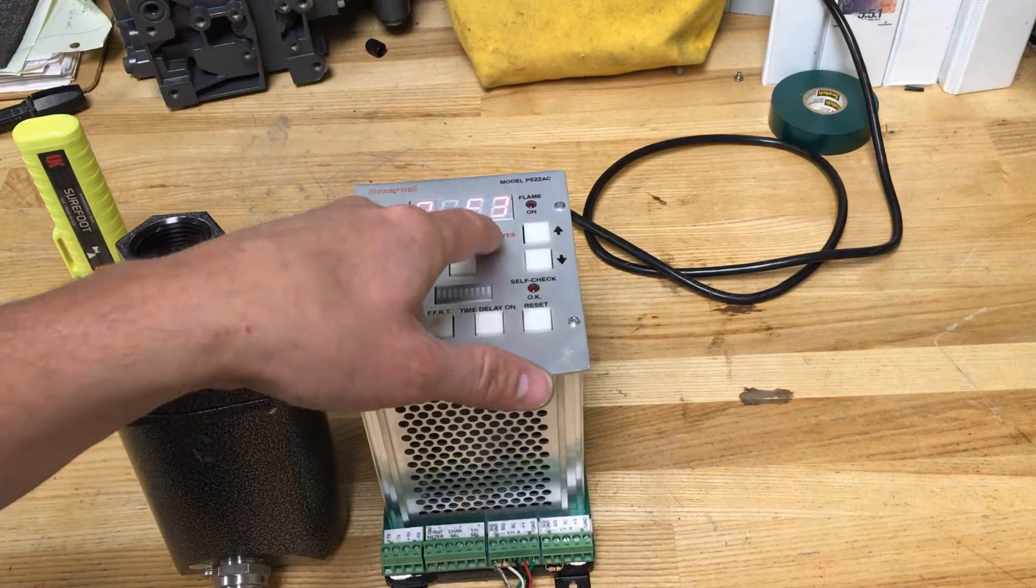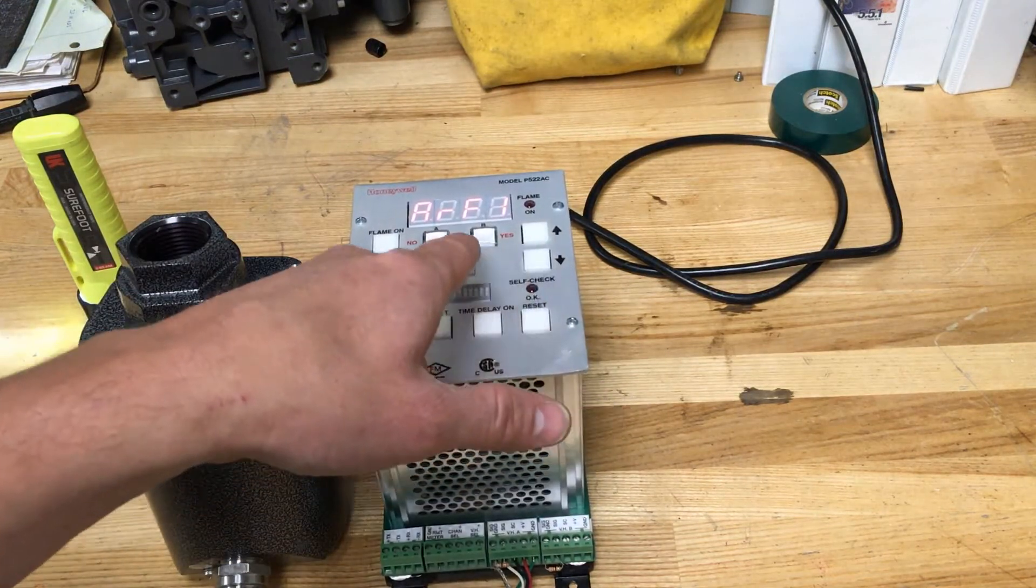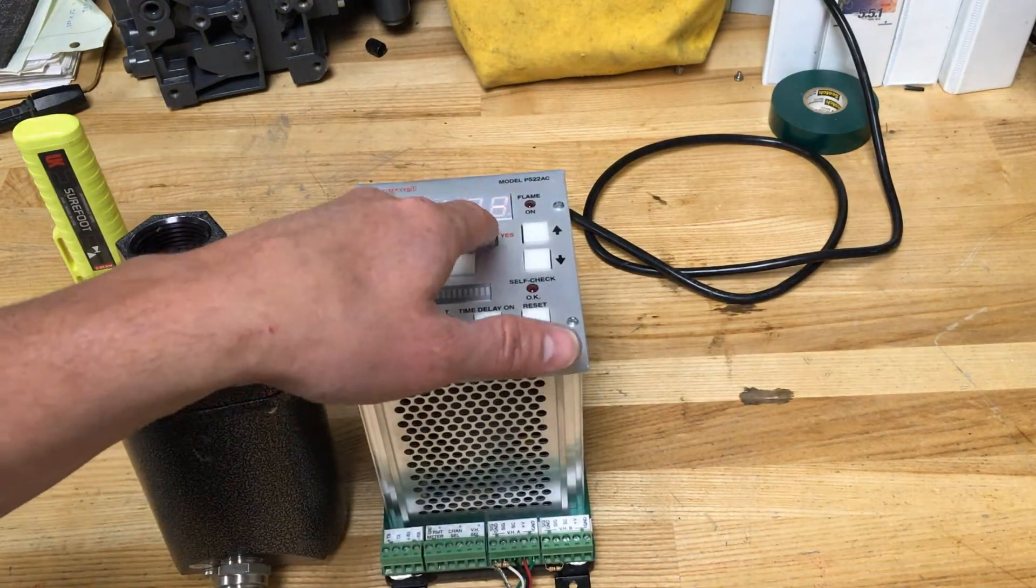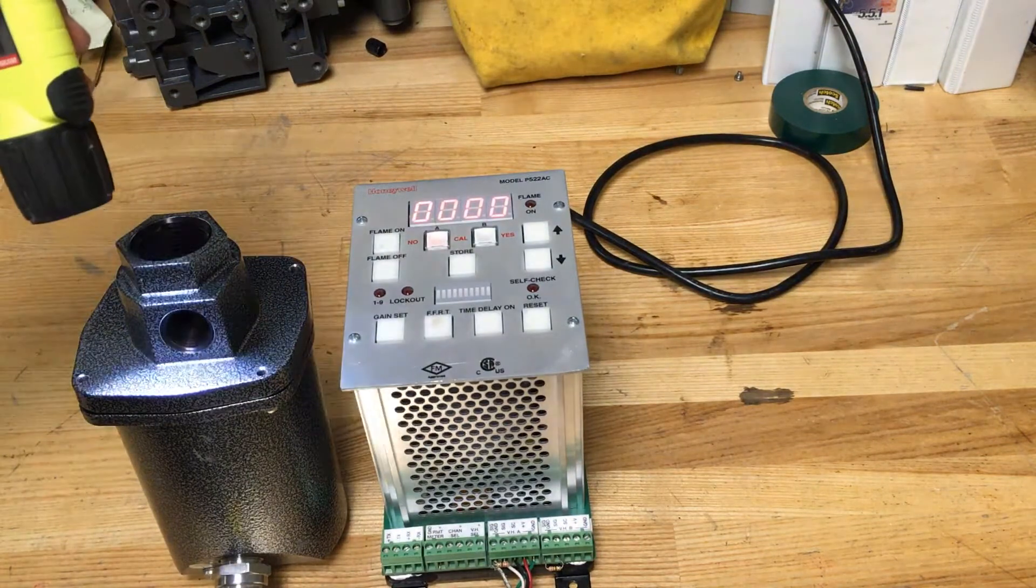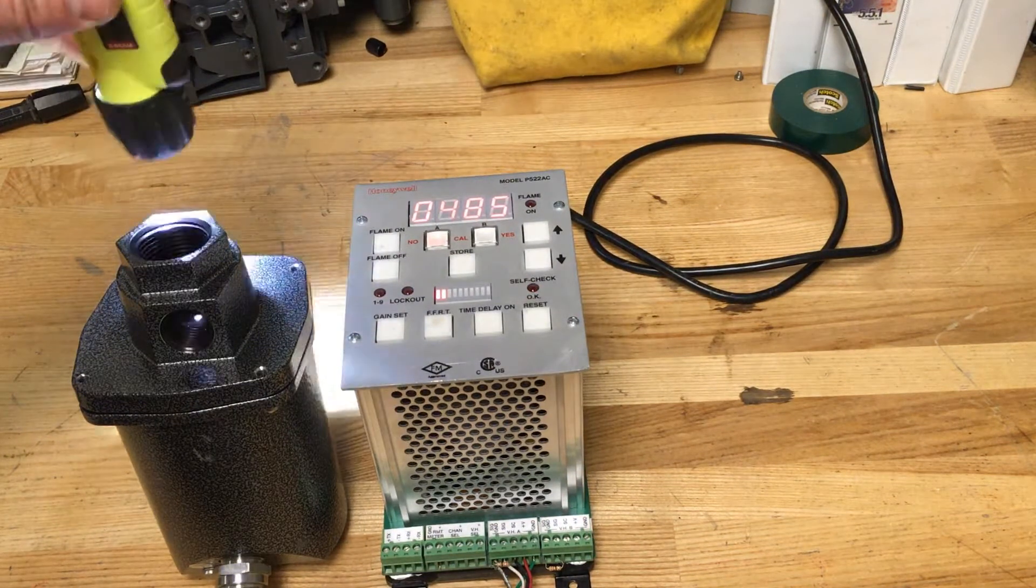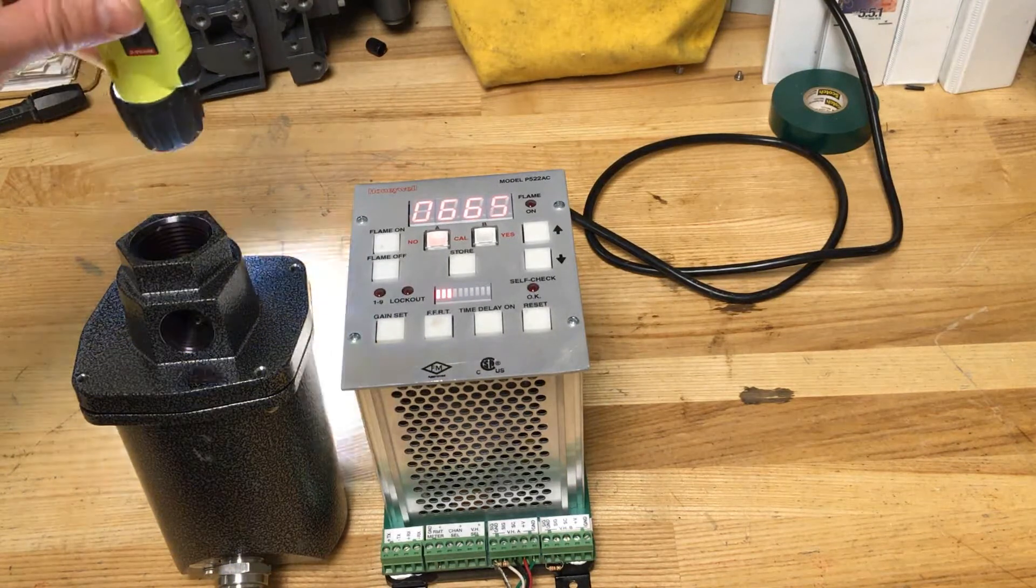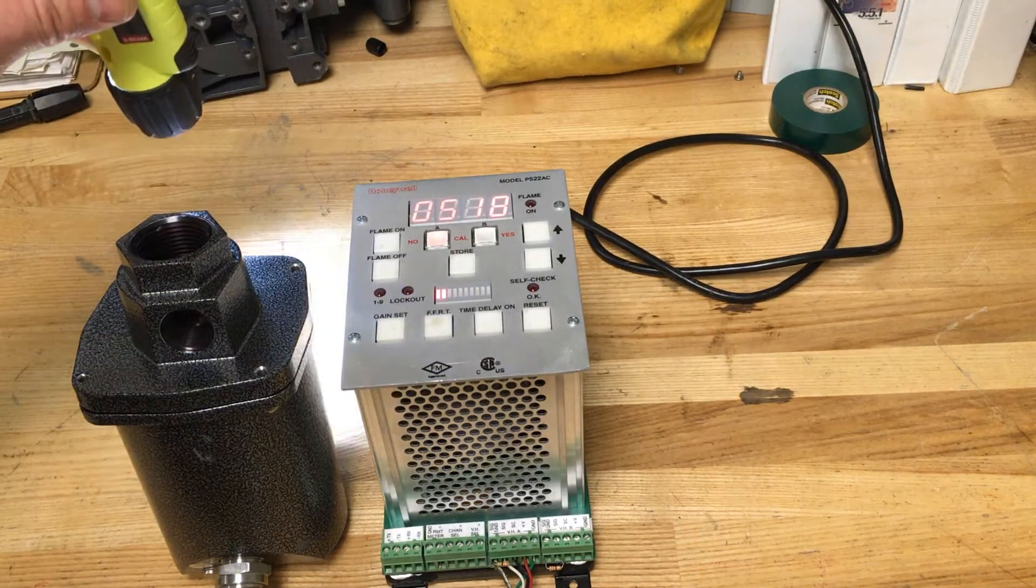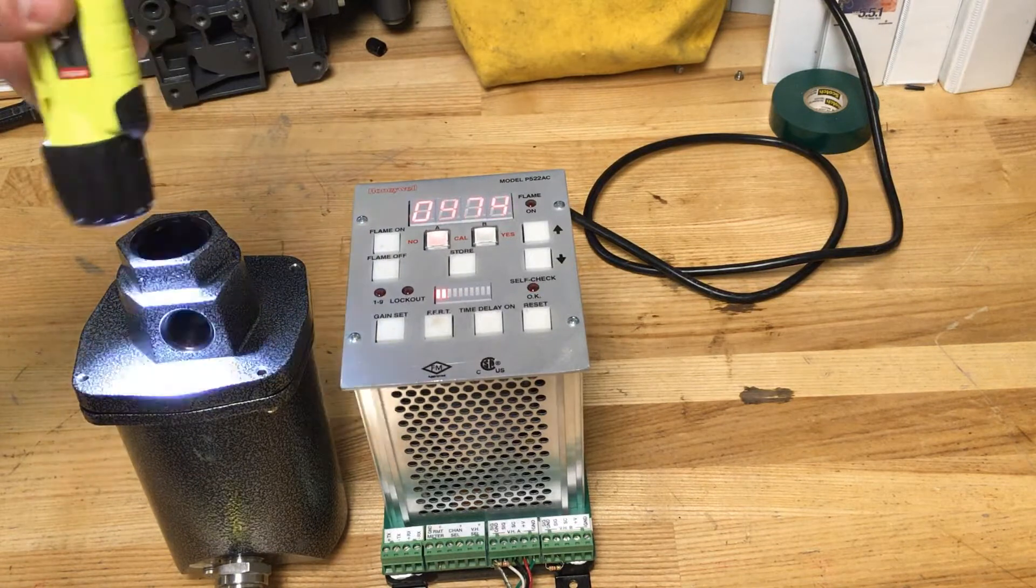By dropping the IR filter value, it lowers the frequency cutoff which allows lower frequencies to trigger flame detection. Increasing this value will raise the frequency threshold requiring higher frequencies to trigger an IR response.